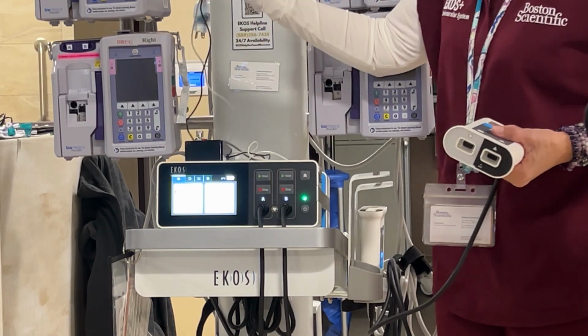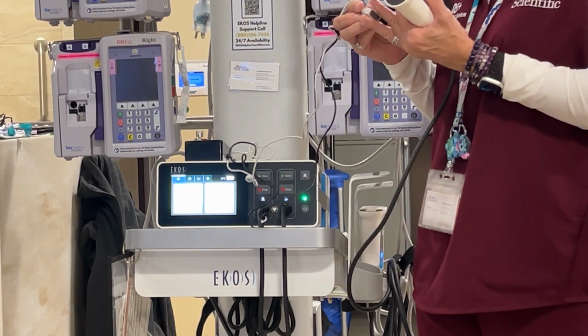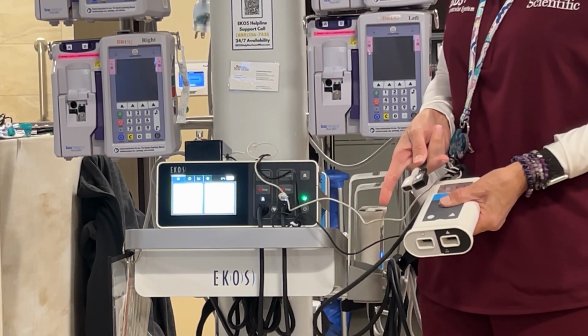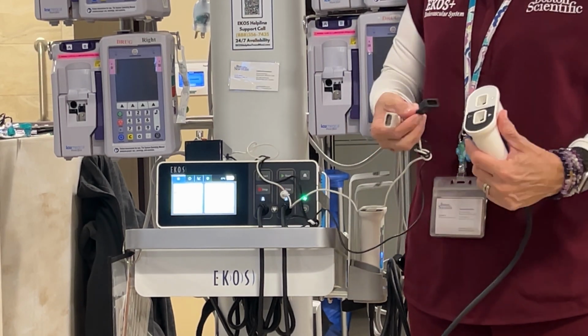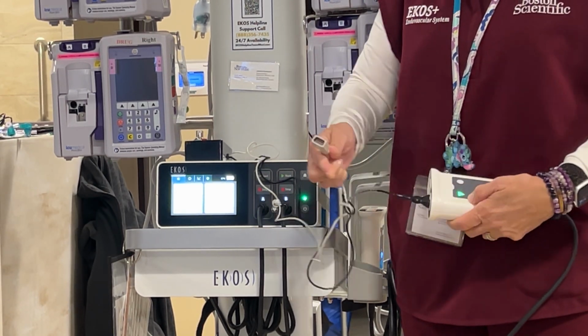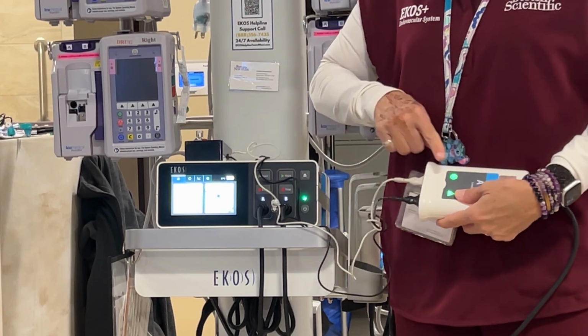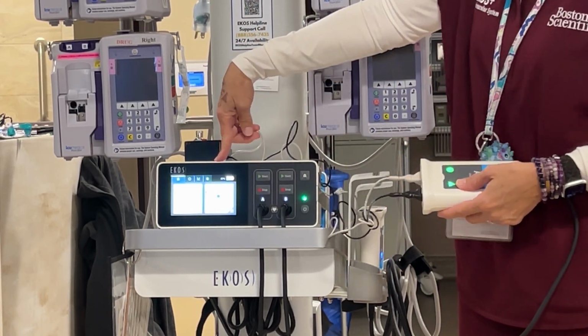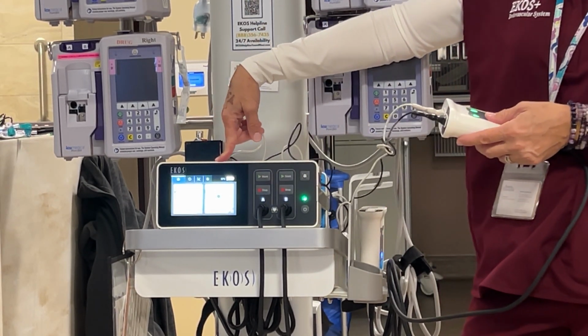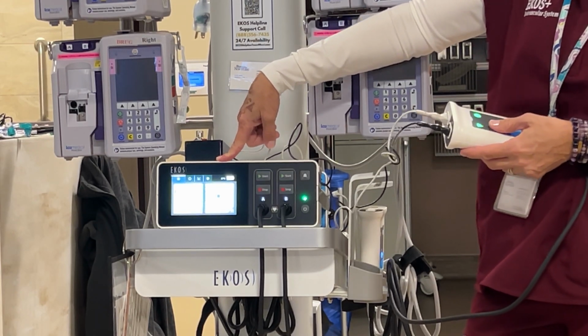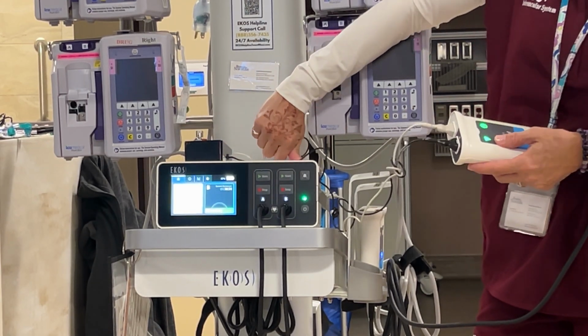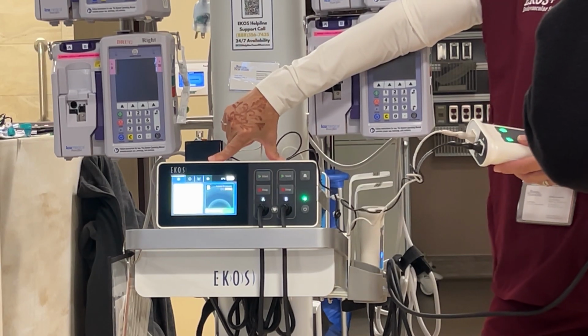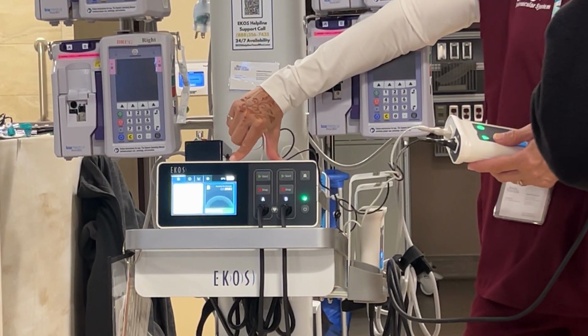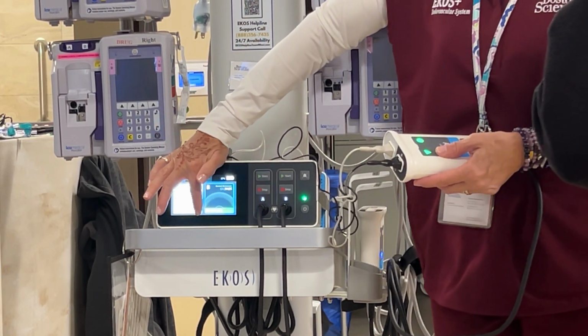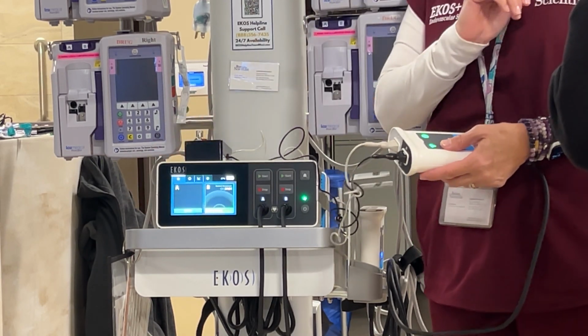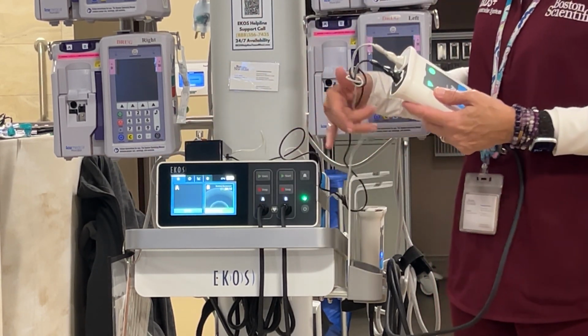So I am going to take a simulator with the same connectors, black triangle, gray circle, only one way to do this, and we just plug them straight in, lights up green, so now it says it's ready, but we actually have to hit the start button for it to start delivering the ultrasound therapy. So we hit start, it says it's running, it gives us hours, minutes, and seconds on the screen. If we're not using the second channel, the other channel will be deactivated, so there's no information on there.